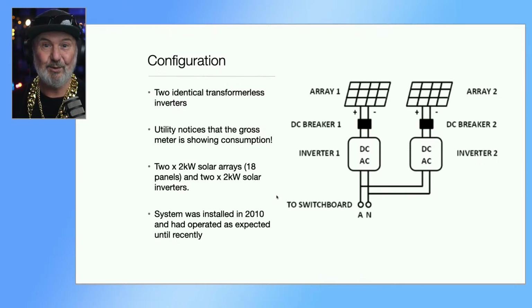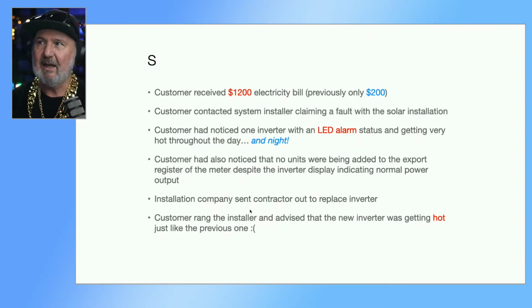Now something is very wrong, okay? Something is very wrong at this point. The customer, as I said, their bill went up massively. They noticed there was a fault light on the inverter. It was hot to touch, one of the inverters, night and day, and there were no units being exported. And the customer rang the installer and advised the new inverter was getting hot, just like the previous one. So nothing was done with the second one.